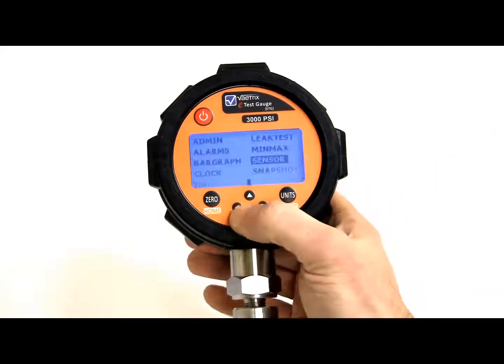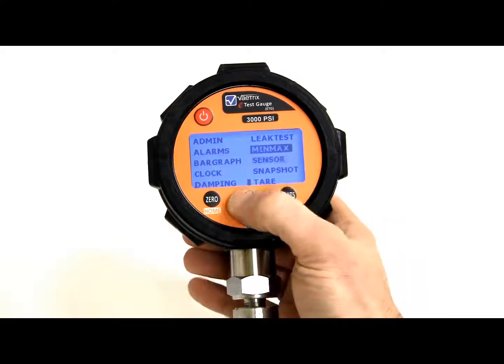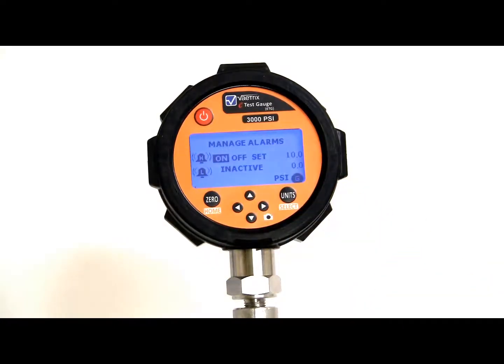Alright, so let's dive into alarms since you saw the screen turn red and flash alarms. So right now, I have an on high alarm set at 10 psi. Notice, when I went to absolute mode, which is around 14 psi, the alarm trips.